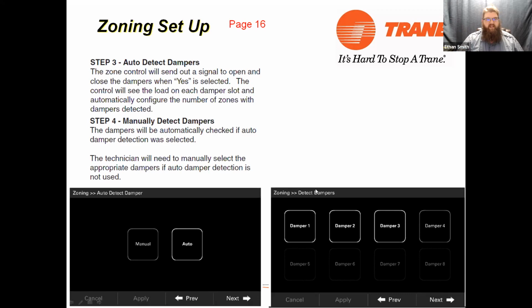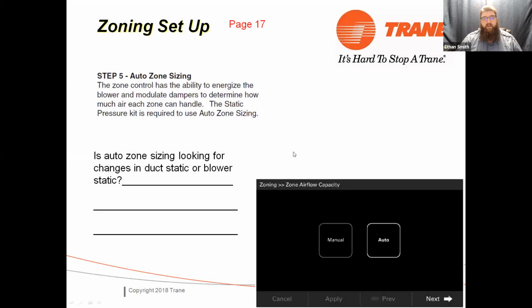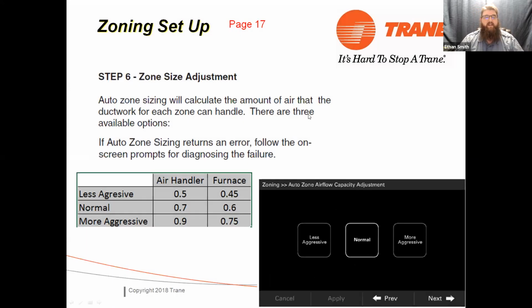You can manually select this. However, this is a really good idiot test on your first setup to make sure that everything got wired up right. You can walk around, make sure all your dampers are opening when they're supposed to be opening and closing when they're supposed to close. After that, it asks you if you want to do your auto zone sizing. Strongly recommend this be done. Your auto zone sizing is going to use that static pressure sensor to determine how much each zone will handle. It does this through a process of running that blower motor up and looking at that static pressure sensor as it runs the dampers open and closed.